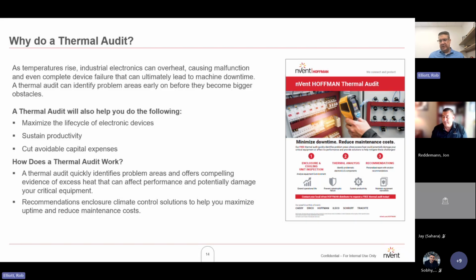Yeah, and maybe, how often do you recommend doing a thermal audit? Obviously you need to have a baseline and some way to track that process. Is this a once-a-year thing, once every other year, or is your answer, it depends on the environment you're in? Well, I would say that once you do a thermal audit on an enclosure and you've identified a potential issue, then let's say we address that challenge and put some solution on there. It wouldn't hurt to readdress that at a later point in time. But if a panel has been upgraded, that would be a great time to do an audit.